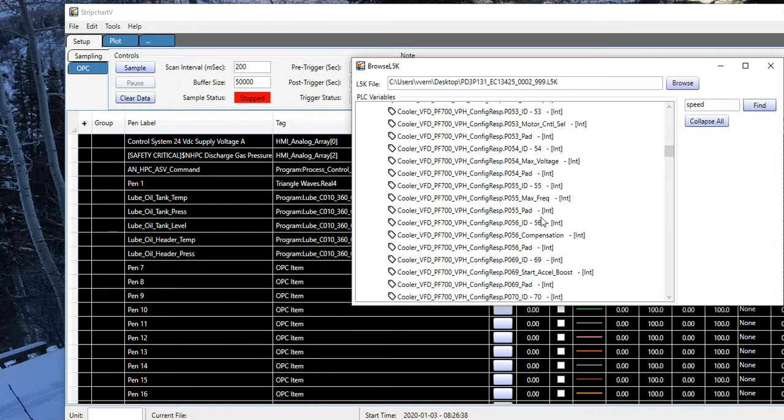we would then browse that sham 4 and look for a pilot setpoint pen. That might be in the fuel routine, and we might be able to find it in here somewhere. There's some pilot stuff, but yeah, here we go. Now we've just converted it to a new pen that actually exists in sham 4.